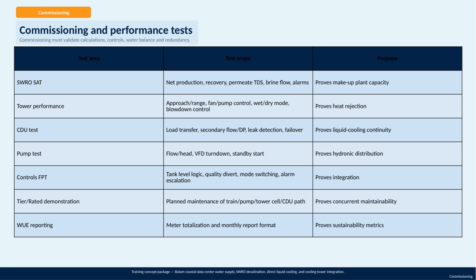The CDU test ensures liquid cooling continuity by validating load transfer, secondary flow and differential pressure, leak detection, and failover capabilities. For the pumps, we test flow rates, head, variable frequency drive turn down, and standby start to prove reliable hydronic distribution. Controls factory performance testing confirms integration by validating tank level logic, quality divert, mode switching, and alarm escalation.